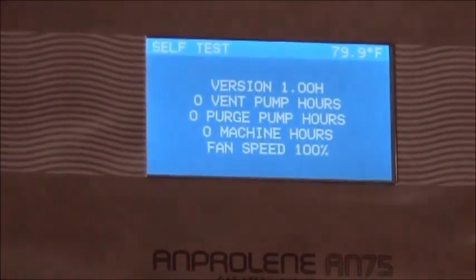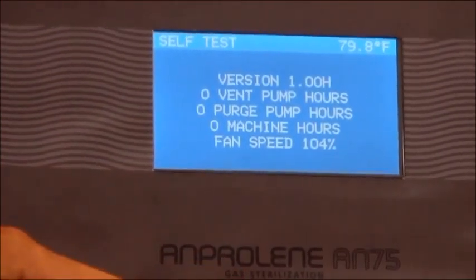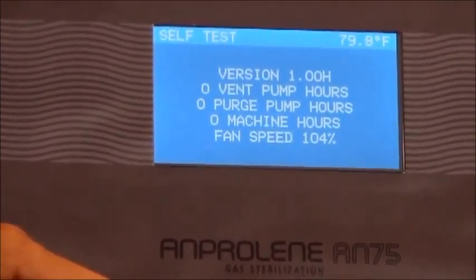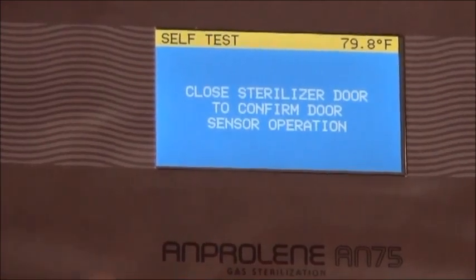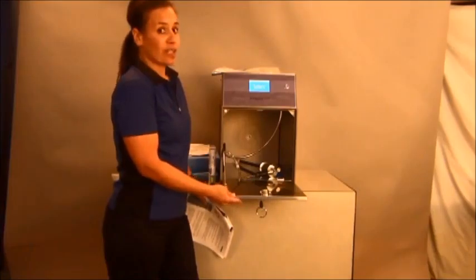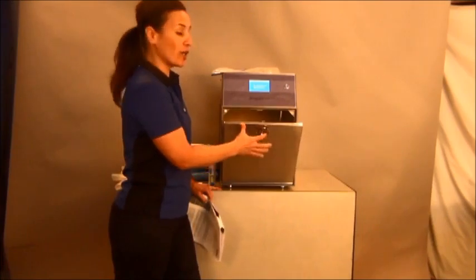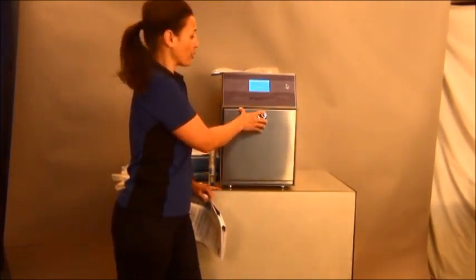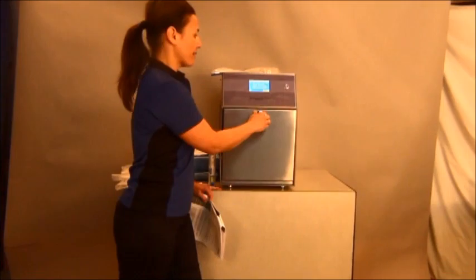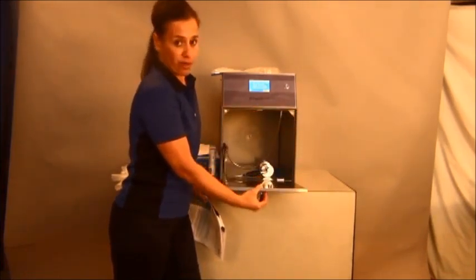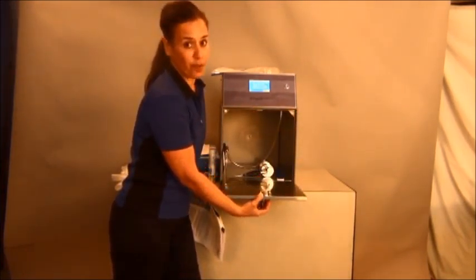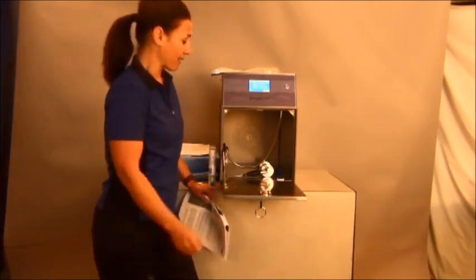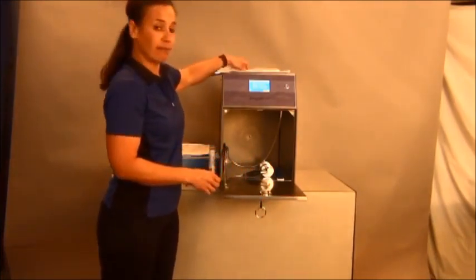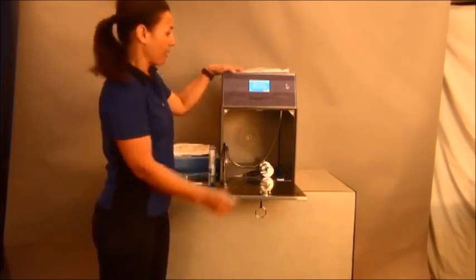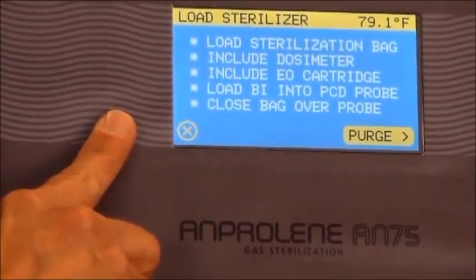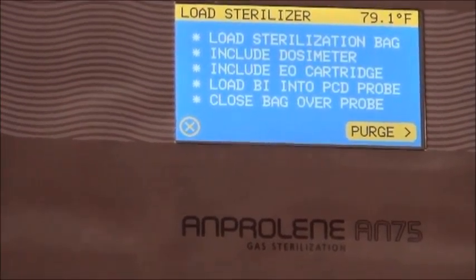It will test the pumps of the sterilizer to make sure they are functioning correctly. It will also test the door sensor. So at this point in time, I need to close the sterilizer to verify that the sensor is working. Self-test passed, and now the sterilizer will tell you the next steps to follow, which are loading the sterilization liner bag. I have all of my items ready to load the sterilization liner bag. It also states here on the display what items are needed.